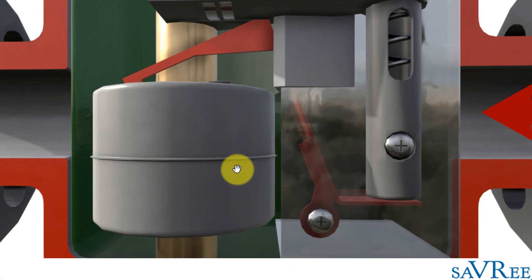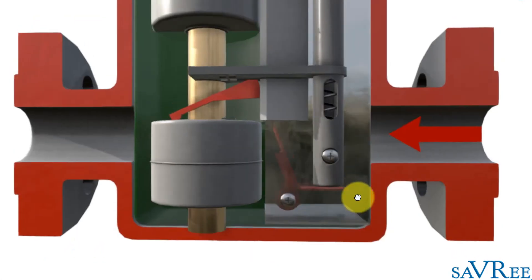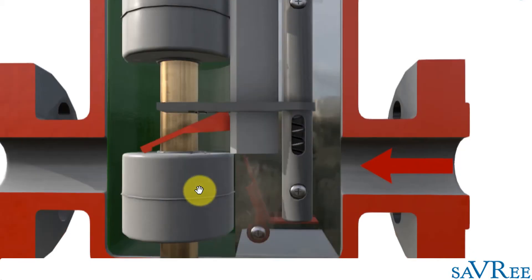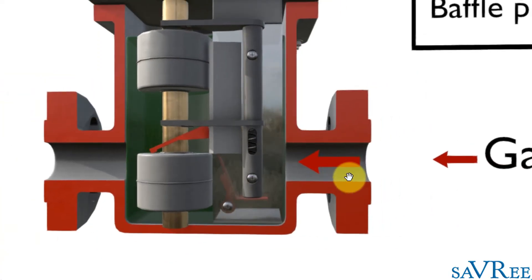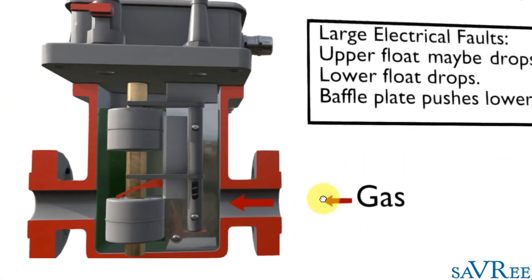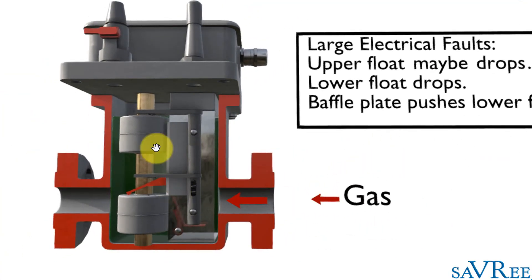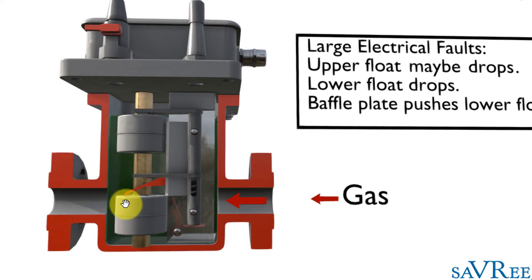Notice I said shut down. Obviously there's going to be an alarm as well, but we're going to shut down the transformer because if the upper float is up and it's just the lower float down and the baffle plate pushed the lower float down, those combinations tell us that that is a big fault and we need to shut the unit down.